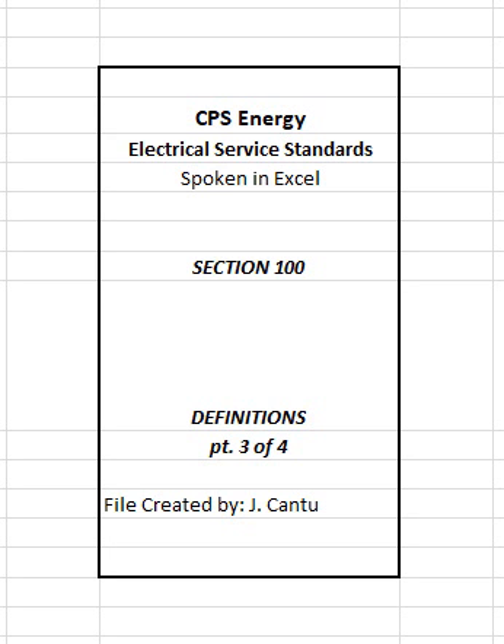Where there is a point of junction between CPS Energy service drop conductors and customer's service entrance conductors, the point of delivery will be at that junction, service head. Where CPS Energy has existing service conductors continuous and unbroken to a meter socket or enclosure, the point of delivery will be at the load side of the meter socket or load side of the metering current transformers.